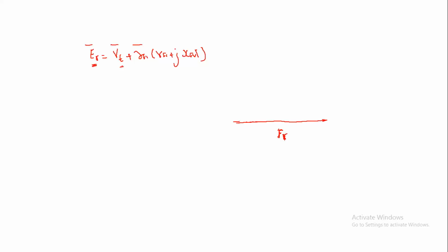Now remember one thing. Here Vt, Ia are per phase, because resistance Ra is 1.2 ohm per phase, XL per phase, and phasor diagram quantities are per phase. So ER you are getting is a per phase value. This is not line value. So per phase is 415 line value divided by root 3, about 230 or 240. Plus IaRa plus jXL drop. This armature leakage impedance drop you have to add. After adding, you will get a value of about 300 volt.